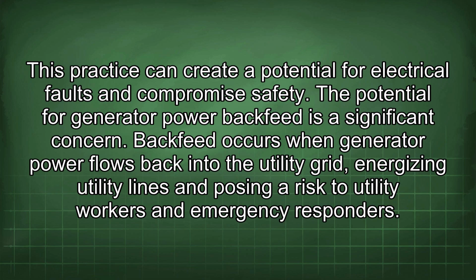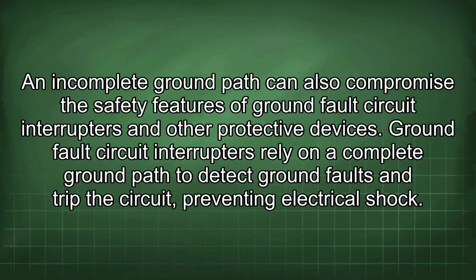Backfeed occurs when generator power flows back into the utility grid, energizing utility lines and posing a risk to utility workers and emergency responders. An incomplete ground path can also compromise the safety features of ground fault circuit interrupters and other protective devices. Ground fault circuit interrupters rely on a complete ground path to detect ground faults and trip the circuit, preventing an electrical shock.